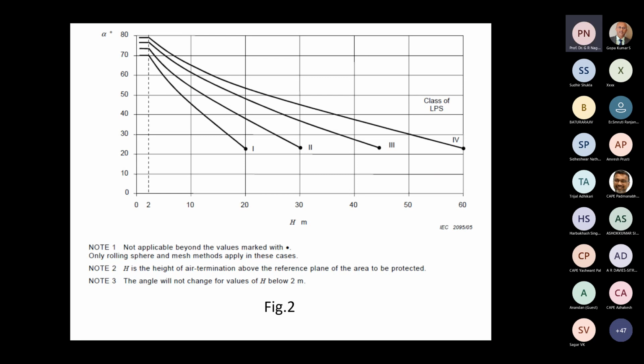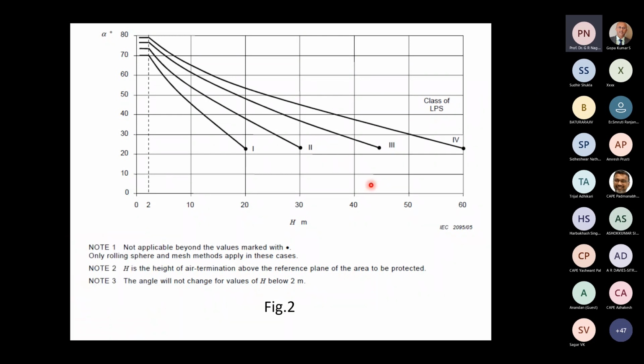So this is the figure taken from IEC 62305, which has been cited earlier. There are 4 curves in this, 1, 2, 3, 4. They correspond to the levels of protection. You can say curve 1 corresponds to a current of 200 kiloamperes, because this can cause the maximum damage to internals. Therefore, the protective angle must be short. And then for taller buildings, and where the current level requirement is a little low, significant protection systems are provided. So I'm not bothered about the lower current levels, but I'm bothered about the higher current levels. Therefore, I can have larger protective angles, about which I will talk presently.